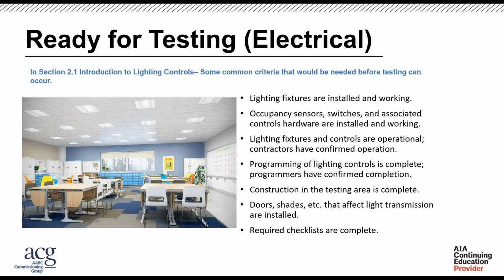It's the same thing with daylighting. You want to make sure you have the right daylighting zones and that it's programmed correctly. A big thing I've seen a lot of times is the photocell either in the wrong location, where it will never see the sunlight, or in the wrong zone, so you're not affecting the fixtures by the window and might be affecting ones farther out. These things should be confirmed and checked prior to coming out for testing, and that's one of the big things I see quite often when we're doing lighting controls testing. Electrically, especially, we'll see the panels, generators, and lighting controls. Sometimes we'll get into paralleling or stuff of that nature, but not too much in educational facilities.